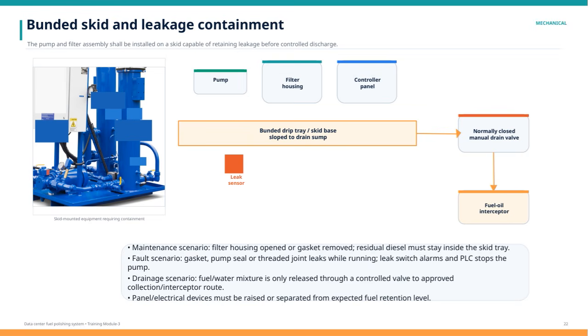If there is a fault, such as a leak from the gasket, pump seal, or a threaded joint during operation, the leak sensor will trigger an alarm and the PLC will stop the pump to prevent further leakage. Finally, if drainage is necessary, any fuel or water mixture is only released through a controlled valve that directs it to an approved collection system or interceptor. Importantly, all panel and electrical devices are either raised or separated to avoid contact with any retained fuel, ensuring safety and reliability in the system.